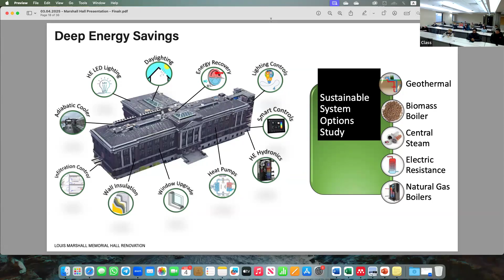So what we ended up doing is a high efficiency natural gas condensing boiler. It's one of the last projects allowed to put new boilers in the state. Moving forward, it's all electric from now on, which causes some issues with everything I just talked about. The other thing with electric is if you want to back up heat your building when power fails, and you're on electric resistance heat, you need a really big generator, and that gets out of control quickly. So that's where we ended up, with our natural gas boiler on our heat pump system.